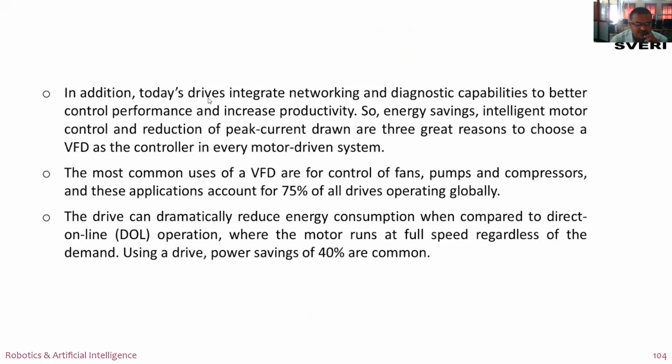In addition, today's drives integrate networking and diagnostic capabilities to better control performance and increase productivity. So energy savings, intelligent motor control and reduction of peak current drawn are three great reasons to choose a variable frequency drive as the controller in every motor driven system. The most common uses of a VFD are for control of fans, pumps, and compressors, and these applications account for 75% of all drives operating globally.